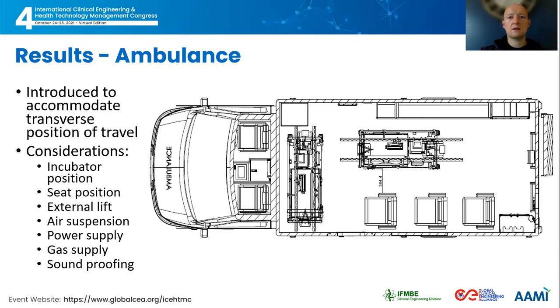With regards to the onboard medical gas supply, each incubator has access to two oxygen outlets supplied by two ZX size cylinders, which is sufficient for 4-hour twin transfers on 100% O2 flow of 10 litres a minute. We also include an automatic changeover valve, a content indicator visible to staff, and positioning of cylinders within the vehicle for even weight distribution. Also, extra soundproofing insulation was installed on the ambulance walls for noise reduction. At the time of this presentation, the ambulance is currently undergoing road testing and will hopefully be roadworthy in the very near future.